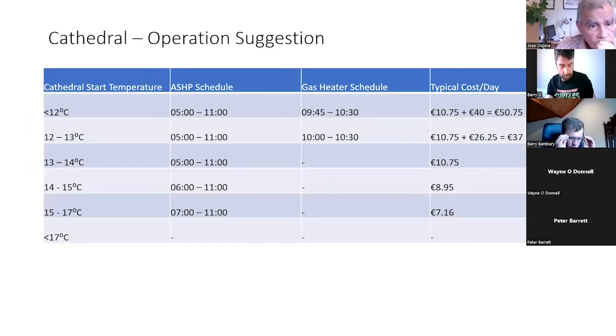So what we've done is looked at how the system performed at various start temperatures, specifically the temperature at around 7 a.m. How close did the air source heat pump come to reaching that 17 degree target, and how much would we need to supplement it with gas heating?